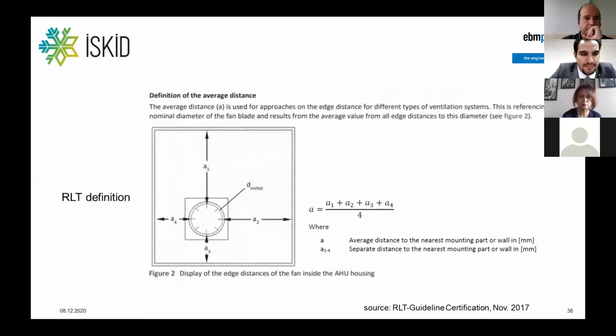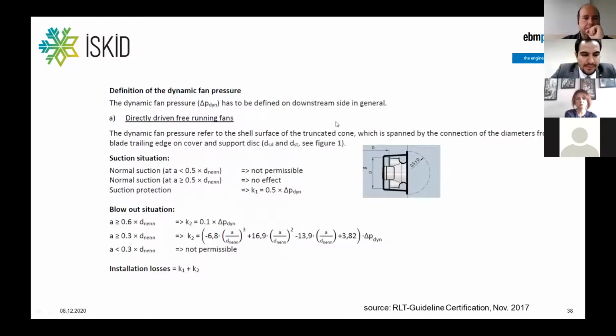And also the position of the fan in a unit has to be comparable, and so there's a formula behind that. It's all the dimensions added up and divided by 4. So you have also here an average distance to the wall. And by doing that, behind these dimensions on the pressure side of the fan, you can then calculate the losses. So if A is above 0.6 times the nominal diameter, you should use the factor of 10% of the dynamic pressure. If it's below a certain dimension, it's not allowed to be used, to be in line with the certification scheme.